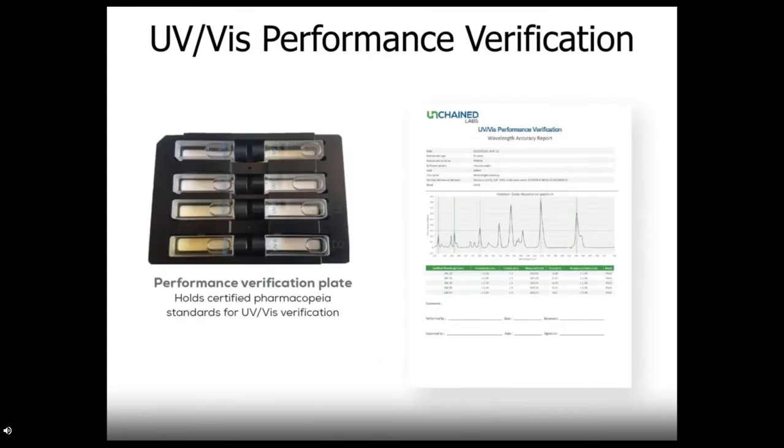And the features don't stop there. We have IQOQ procedures available, and for labs doing manufacturing, quality assurance, and quality control, Lunatic now has a performance verification for new instruments. These tests with certified cuvettes meet the United States Pharmacopoeia and the European Pharmacopoeia guidelines for UVVis spectrometers. The tests and all necessary calculations are completely handled automatically by the software.